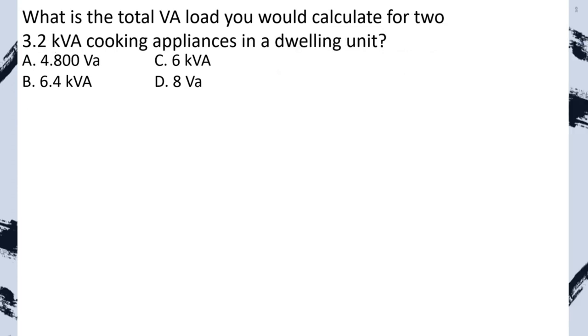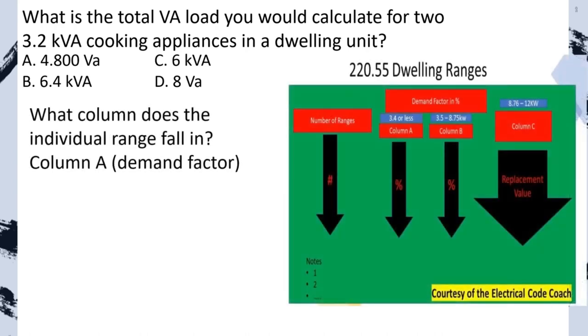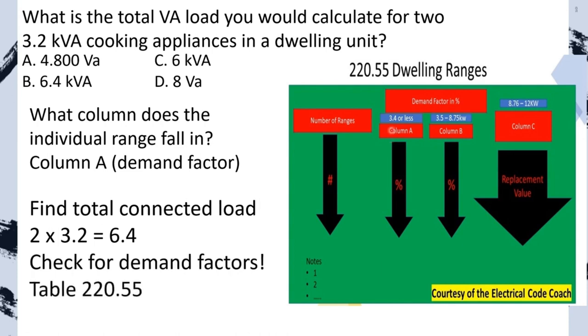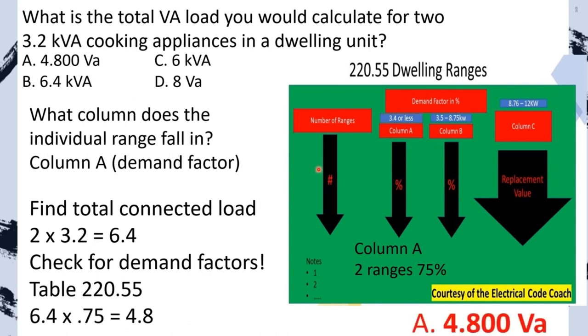Practice problem: What is the total connected load for two 3.2 KVA cooking appliances in a dwelling unit? Individual range falls into Column A. Find total connected load: 2 multiplied by 3.2 KVA equals 6.4 KVA. Check for demand factors: from the table, Column A for two ranges is 75%. Multiply: 6.4 multiplied by 0.75 gives our new reduced load. We select A.